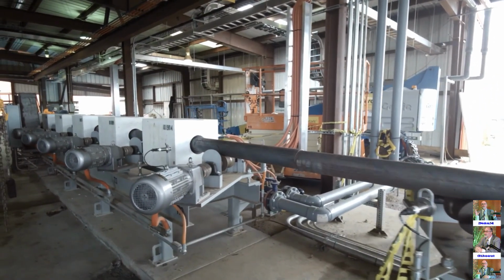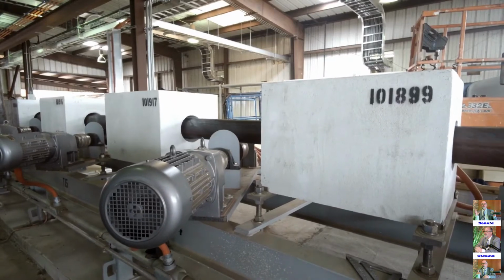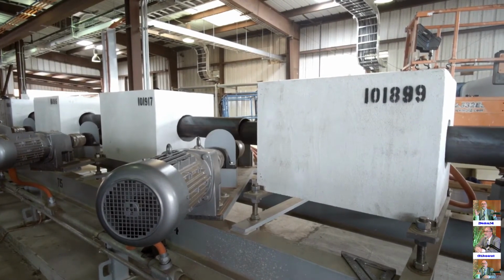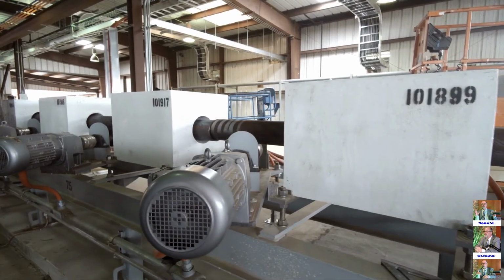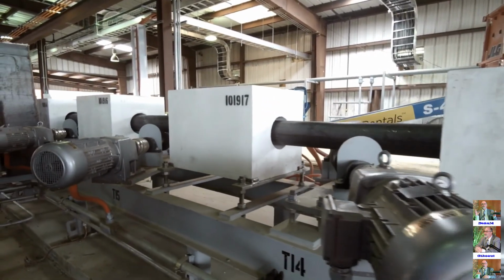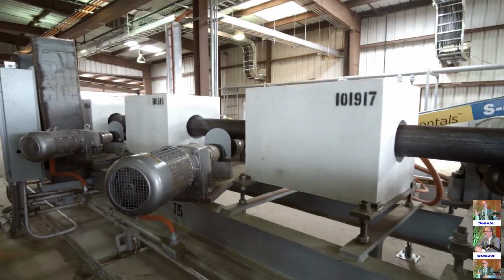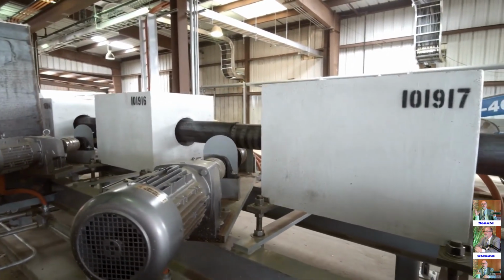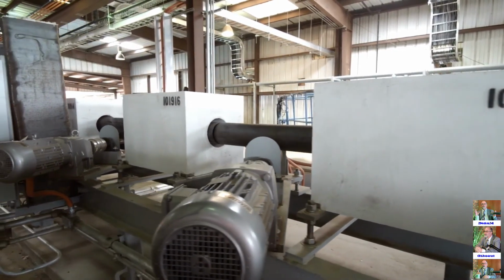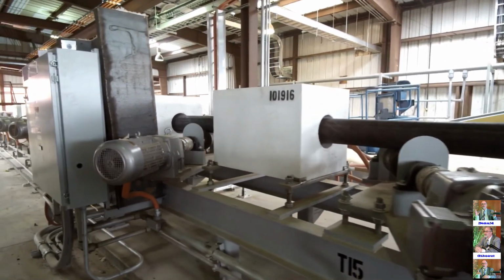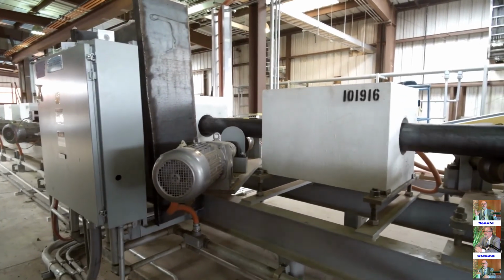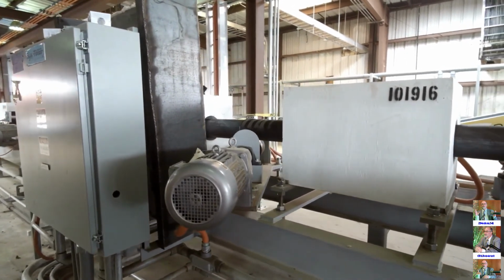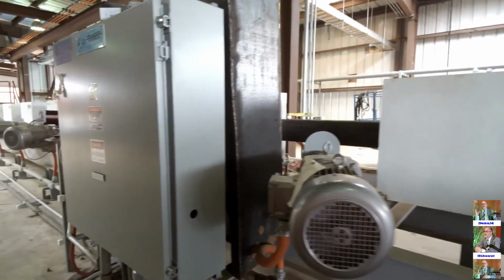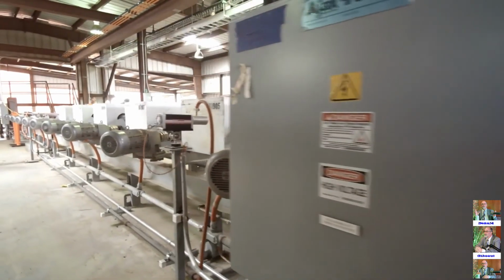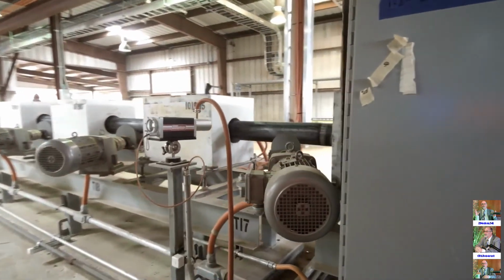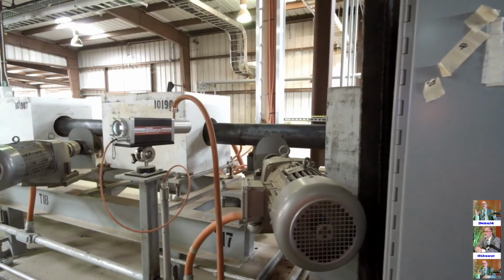And like we talked about that current crowding, we can have, as a rule of thumb, up to a half inch and not really get into overheating the ends. And we're at lower frequency here, as we showed with the FEA. That also helps with that current crowding when you produce a gap between the pipes. But you can see here it's very precision controlled. We like driving every roll. We do have systems with daisy chains together, but when we did a cost analysis, we found there wasn't enough price difference to lose some of the functionality of having individual drives here, especially to keep everything driven and maintain this butting together.